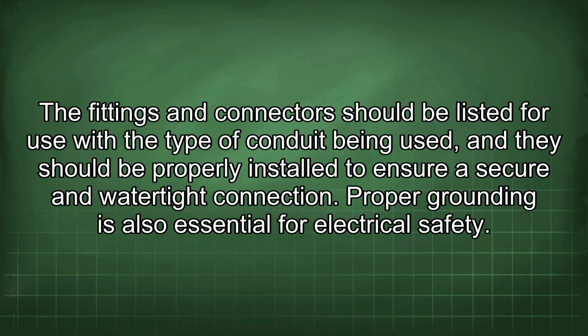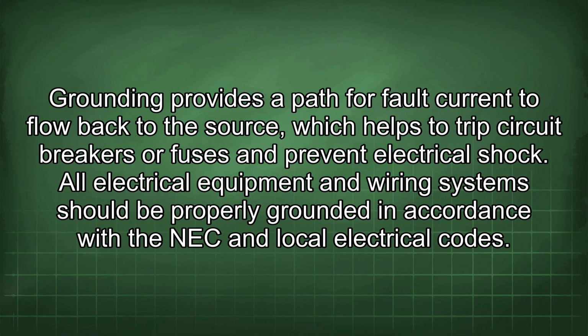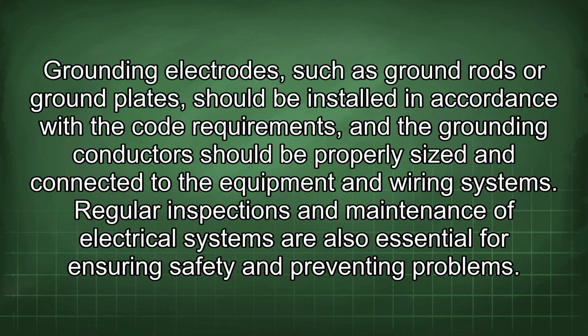Proper grounding is also essential for electrical safety. Grounding provides a path for fault current to flow back to the source, which helps to trip circuit breakers or fuses and prevent electrical shock. All electrical equipment and wiring systems should be properly grounded in accordance with the NEC and local electrical codes. Grounding electrodes, such as ground rods or ground plates, should be installed in accordance with the code requirements, and the grounding conductors should be properly sized and connected to the equipment and wiring systems.